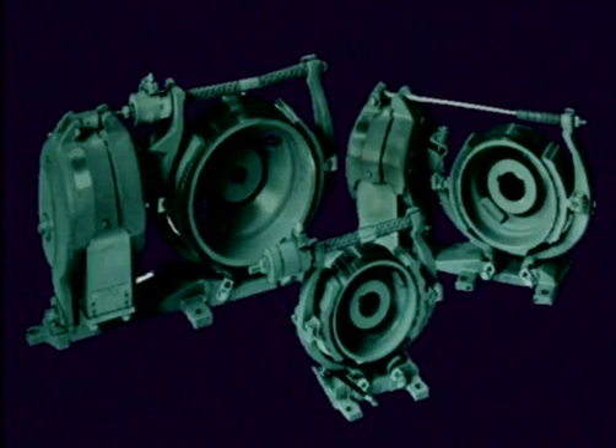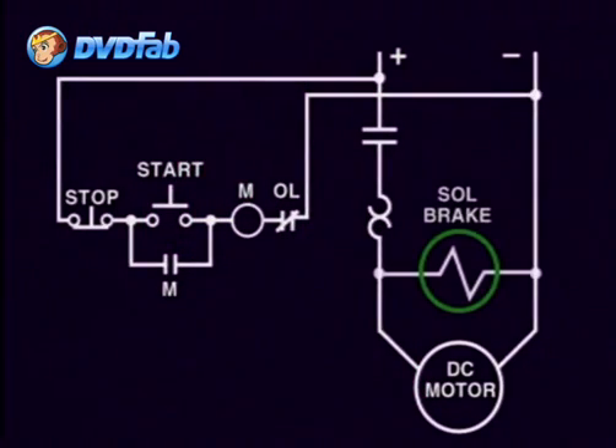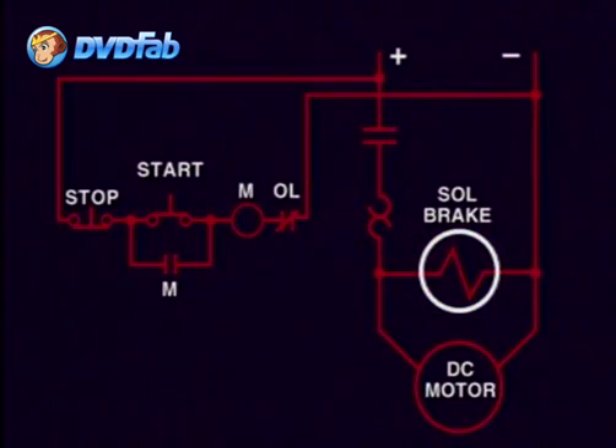Deceleration of a DC motor to a stop can also be accomplished with electromechanical brakes, of which the most commonly used is the friction brake. The friction brake is solenoid operated and basically works like an automobile brake system. It is connected across the positive and negative terminals of the motor in such a way that if the motor is started, power will be available at the solenoid and the brake shoes will be pulled by the solenoid action, thus removing all friction from the drum. This allows the motor to rotate freely.